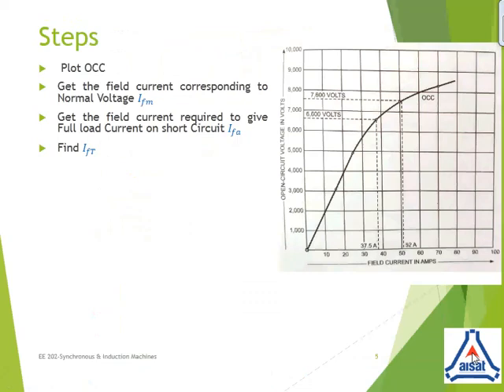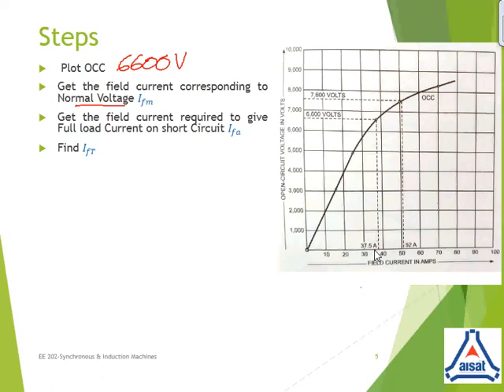Now, we will get into the numerical steps. The very first thing is, after the plot of OCC, you need to get the field current which corresponds to the normal voltage. Because, here it is normal voltage. Why? Because, it is given in the question that you need to find the full load voltage regulation. The field current which corresponds to this normal voltage is denoted by the letter IFM. And IFM value over here is, the normal voltage from the question is nothing but 6600 volt. Corresponding to that 6600 volt, what is the field current corresponding to that? It is coming over here and it reads as 37.5 ampere. That is the first data we are getting, IFM as 37.5 amps.